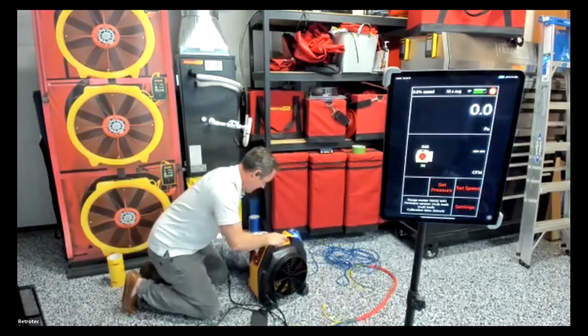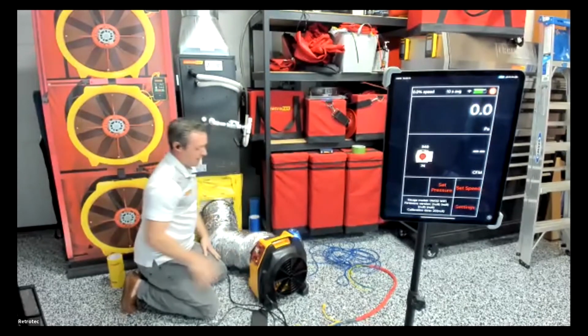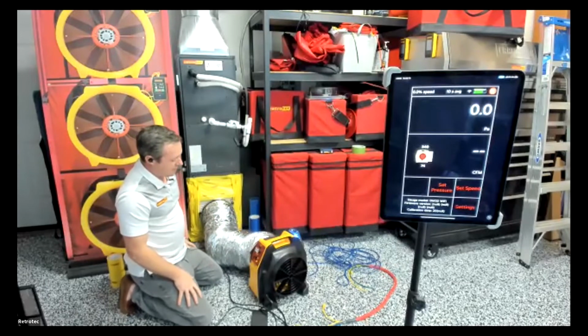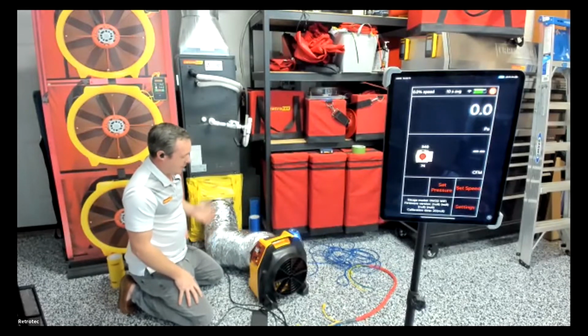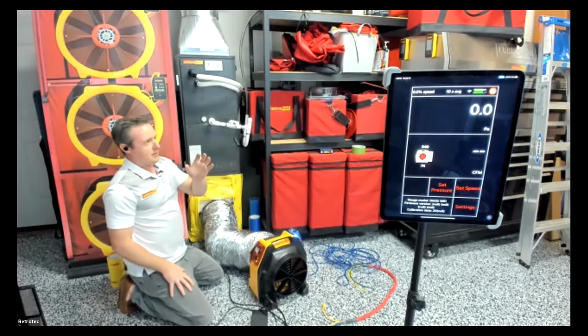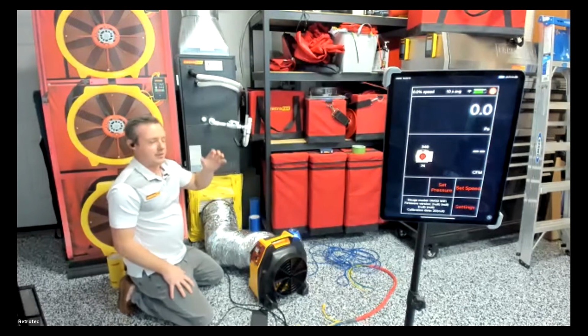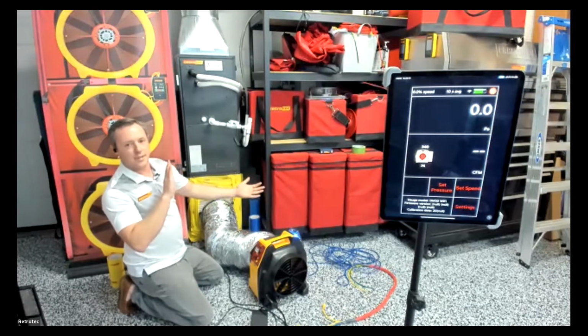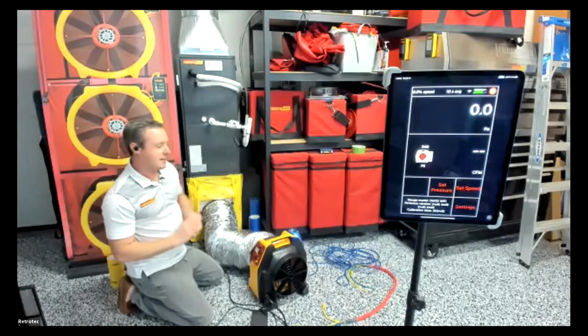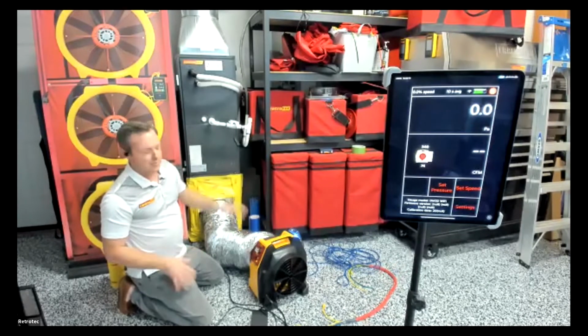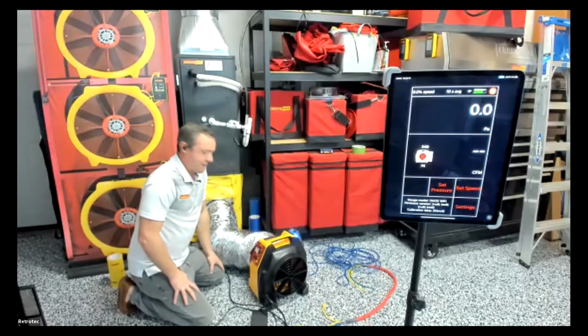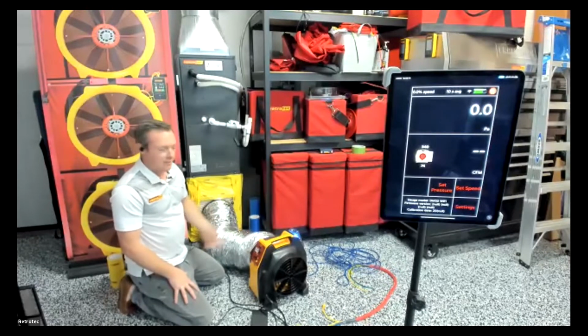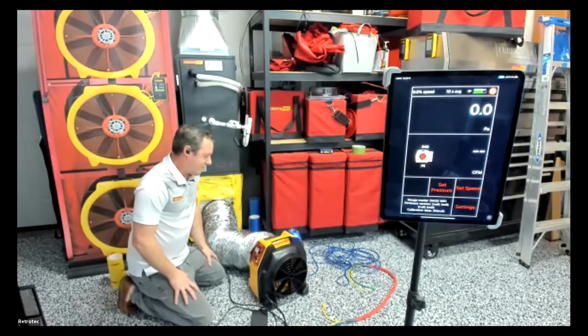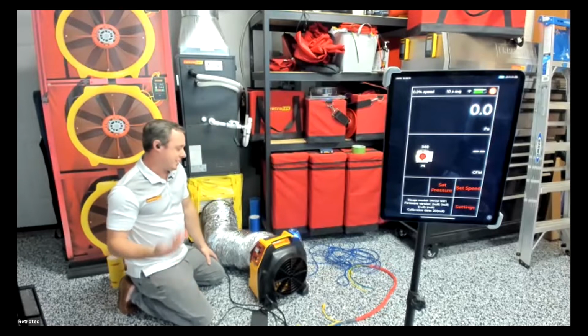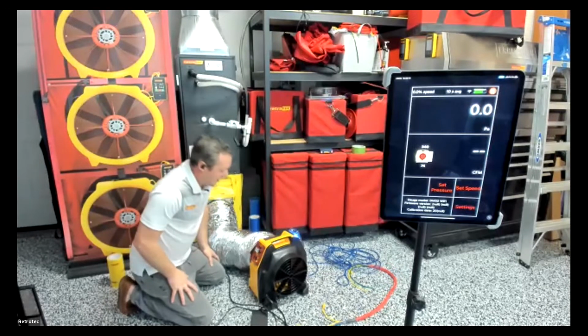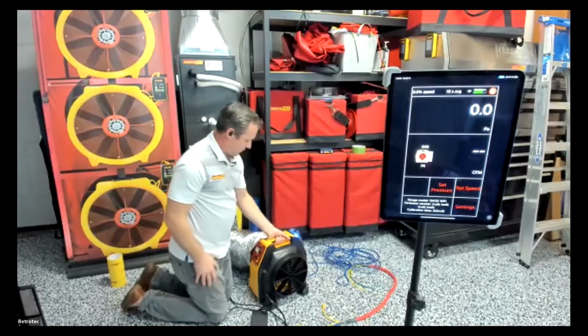This is what I prefer to do. I always prefer to depressurize the system, mainly because as we have our supplies and returns taped off, it's going to pull that tape tighter to the register rather than blow it off. When that happens, it can be frustrating because then you have to walk around the house and figure out what came loose. So there's less chance of that happening when you run a depressurization test. So we will run it.